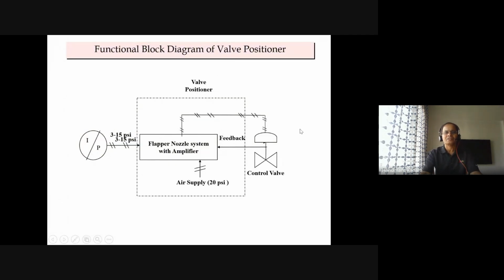This is how it works: the I2P signal comes from the control loop. This is a mechanical system, flapper nozzle system, and the control valve gets operated. Air signal is here, and position feedback is coming back. This is a basic pneumatic, mechanical system, with air supply at 20 psi, and this dotted portion is the positioner.